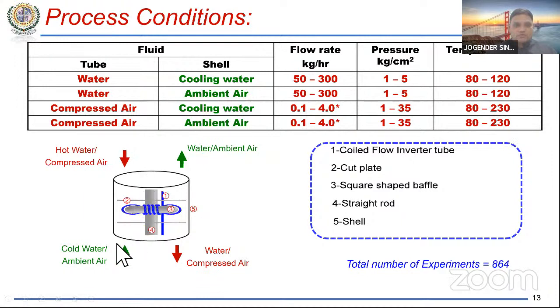So this is again to understand how the flow was taking place. The hot fluid was coming from the top inside the tube, and the cold fluid was going from the bottom, and that's how it was a cross flow arrangement. And for design perspective, you can note down that this whole arrangement we are calling the coil flow inverter tube. This blue color is the coil flow inverter tube. The second, which is like a circular plate, is known as the cut plate. It also acts as a baffle. The third one is a square shaped baffle around which we have rounded this tube, and this straight rod gives strength to the whole structure. It is also acting as a baffle, and the fifth one is acting as the shell.